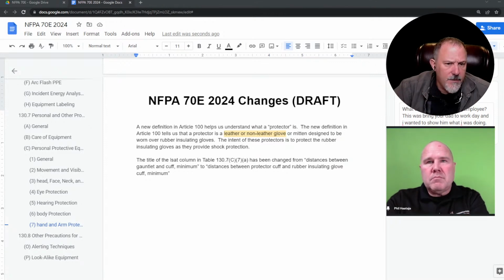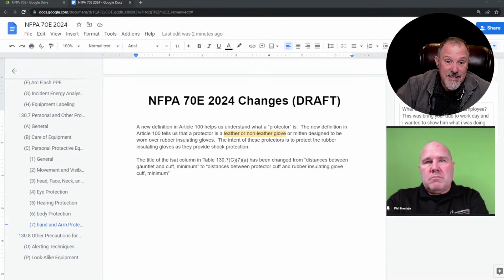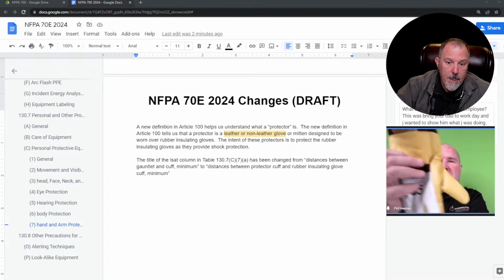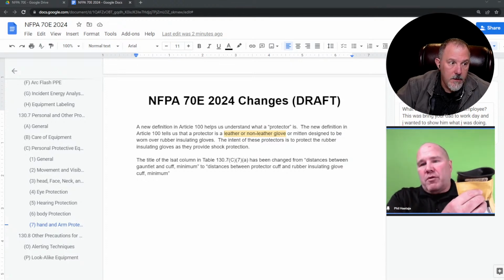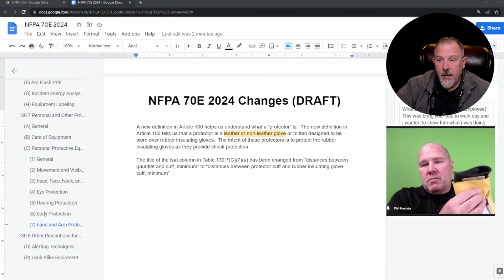And a class 4 glove goes up to a maximum AC use voltage of 36,000 volts, with a minimum of 4 inches - that's a minimum, because these are 11-inch gloves. You can get class 00 14-inch gloves too.